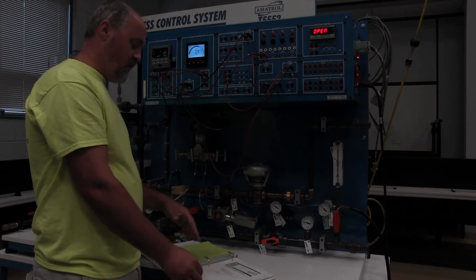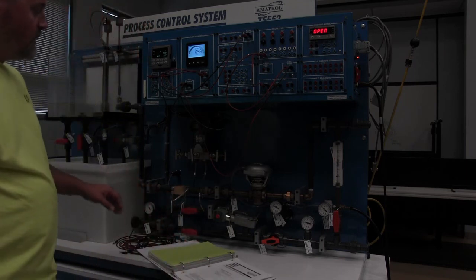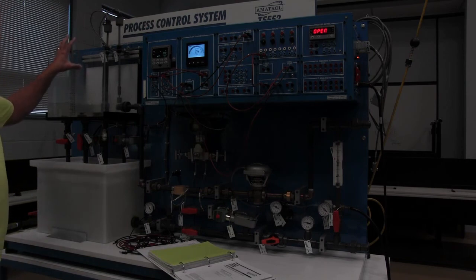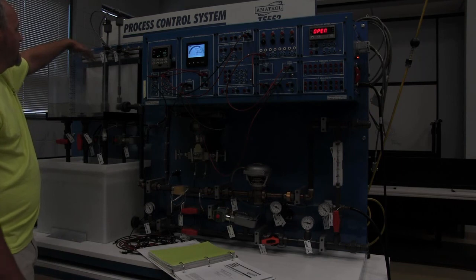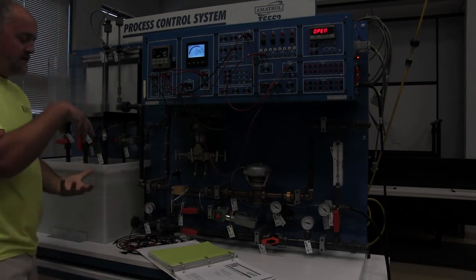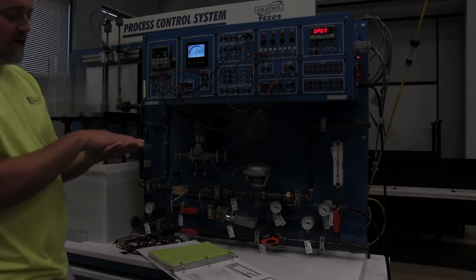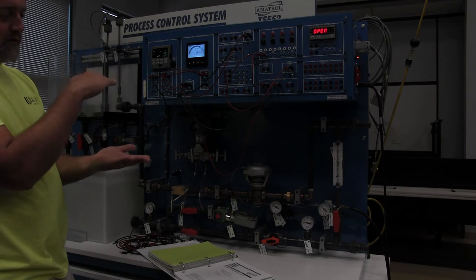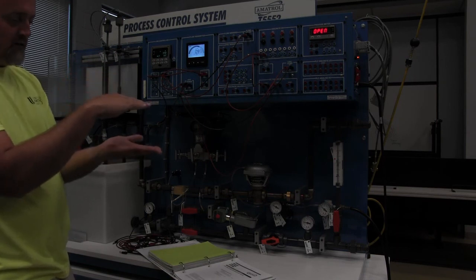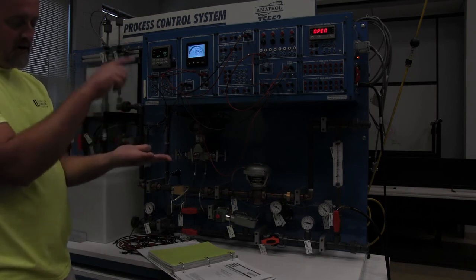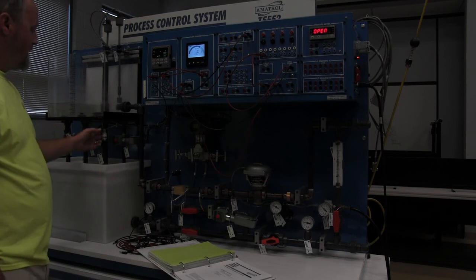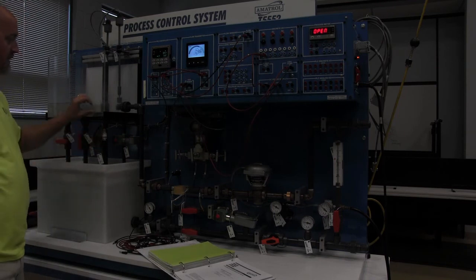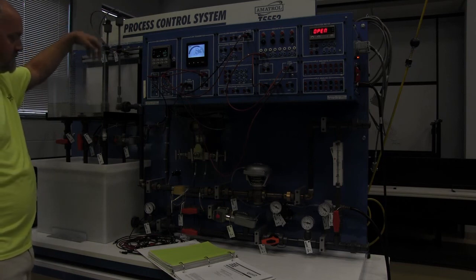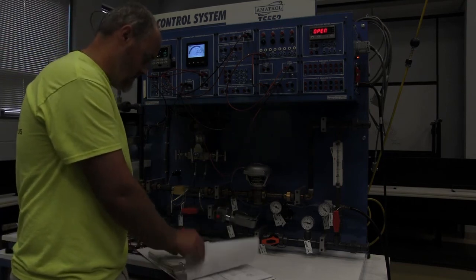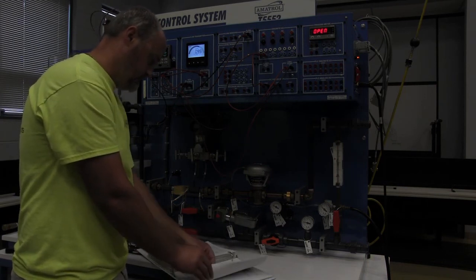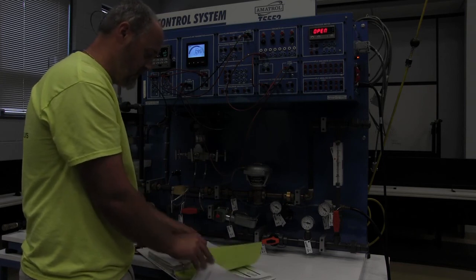This next section is an ultrasonic level measurement and control. We do not have the ultrasonic transmitter for this trainer. If you did, it would mount up here. It would sit on top and shoot a beam back and forth, and it takes a measurement from the bottom of the transmitter to the level surface by how long it takes for that signal to bounce back and forth, and that will give you your level rather than using a level transmitter on the bottom for pressure. We don't have it, so we're going to skip over that portion. This is just setting it up and calibrating the ultrasonic level transmitter.